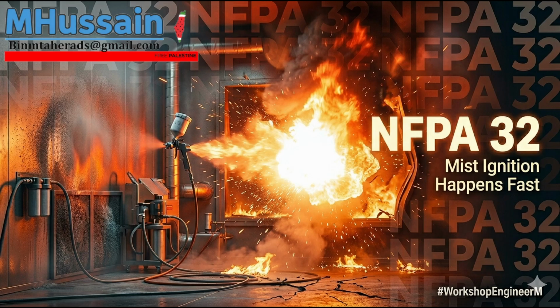How high of a pressure are we talking? We are talking about operating pressures ranging from 700 to over 1,000 pounds per square inch. That is insane. For 70 years, the facility designer's main hazard was just managing liquid spills in a trough or maybe some explosive vapors in the ductwork. And now you are managing high-pressure gas systems. You are intersecting with the ASME boiler and pressure vessel code.